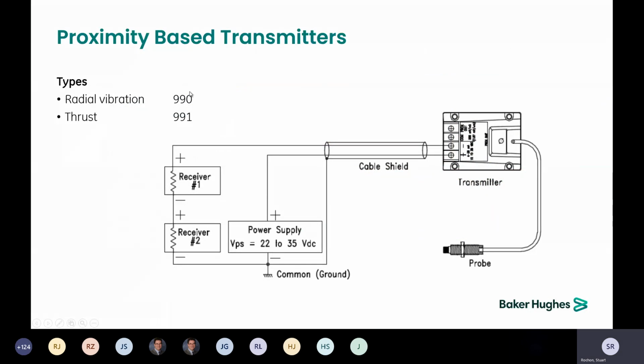For radial vibration with proximity probe, we have the 990 series. There are a number of scale ranges for the 4 to 20 milliamp scaling. Same thing for thrust with the 991. These do require an active 4 to 20 milliamp circuit, so you have to supply the power. That powers up the proximeter and powers your current loop. And here on the 990, 991, you have the common and prox out for reading the dynamic signal. There's also a BNC connector that you can connect to with your portable data collector.